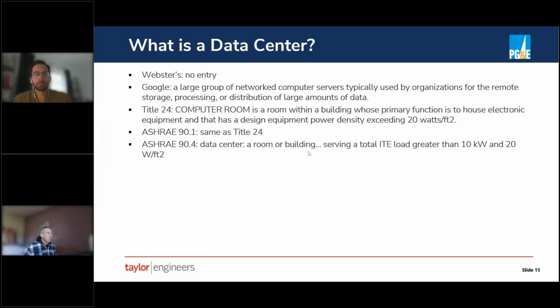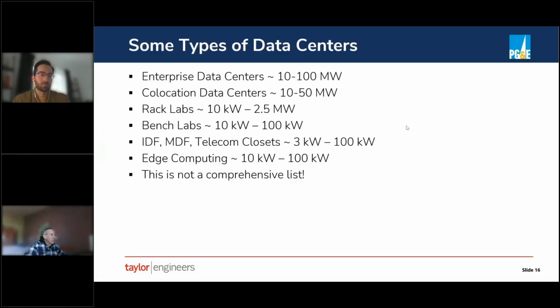And it is any room within a building whose primary function is to house electronic equipment and has a power density exceeding 20 watts per square foot, which, for those of you who have data center familiarity, is not a very high density. Data centers today can easily be 200 watts per square foot or higher. So it's really almost any room dedicated to computers. ASHRAE uses pretty much the same definition. The new data center specific standard from ASHRAE has a minimum of 10 kW, but that's a pretty small number. So data centers can be anything from very small rooms to very large, basically dedicated to computers.